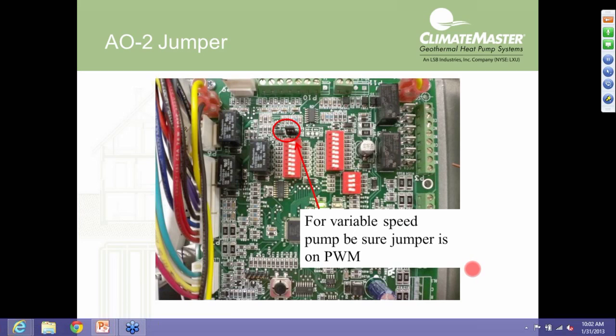So again, this jumper is very important, and if it's in the incorrect spot, it could lead to a lot of frustration until you verify that it was in the right spot. Again, it can lead to LT1 lockouts in the heating mode, high pressure lockouts in the cooling mode if it's not in the right spot. So I really stress, if you're having an issue with the pump or the valve not working like it should, one of the very first things that needs to be done is verify this jumper is in the correct spot.